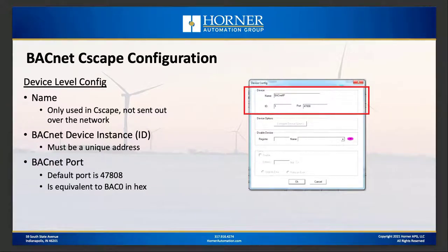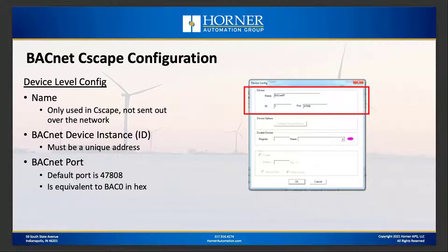At the device level, about the only thing that really needs to be configured is the ID. There's also a name in device configuration, but that name is only used in Cscape and is not sent out over the network. The ID must be unique on the network — choosing one might not be the best choice on a large network since it's probably the most common ID. The BACnet port number defaults to 47808, and typically there's no reason to change it.